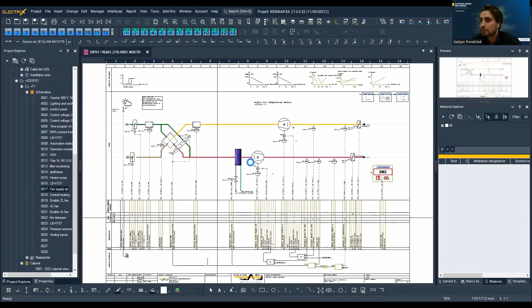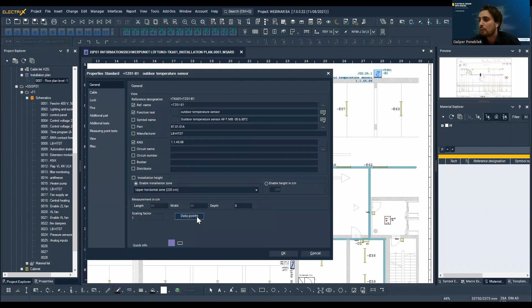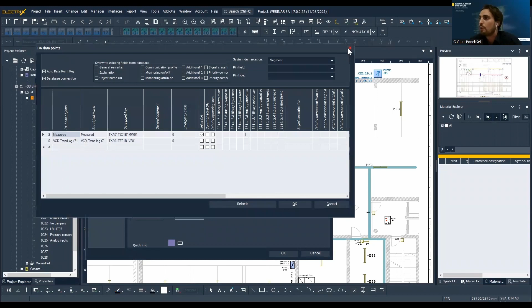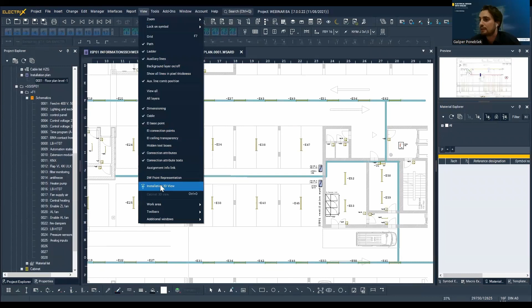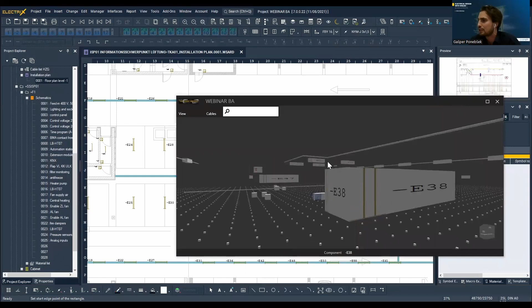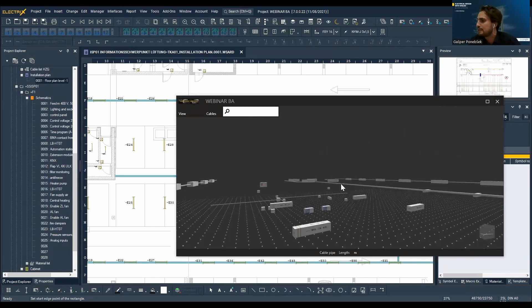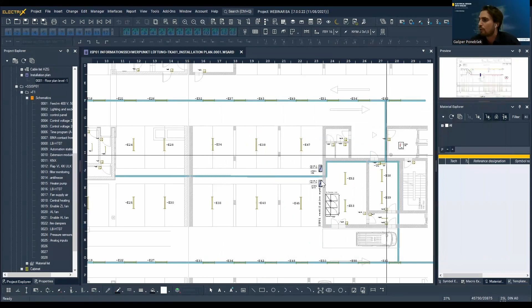So in the installation plan, for example, here we just jump to the installation plan where we have some DWG file, and on this DWG file you can see a lot of elements, and we can open this outdoor temperature sensor, and you can see we have information about the height. So we place this element in its place. It's 3D, and all these elements on the DWG are 3D oriented, actually lying in place. We can check it right now with this 3D overview. Here, all elements are actually lying in the space, and we have exact information about the height. And we can actually put in this cable pipe and make calculations for cables, and then we can generate a very precise cable list.